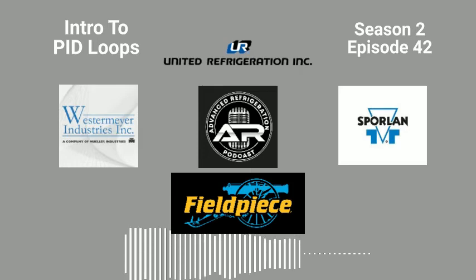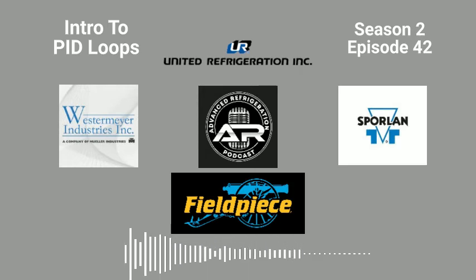With CPC stuff, you're going to control a valve actuator and you're using an EPR board. That EPR board update rate is 15 seconds from the factory, so you need to change it to 2 seconds. So even on CPC, you have a 2-second update rate on the input, a 2-second update rate on the EPR board, and now you have the loop sequence control, which is going to be your main driver of the main PID loop, and it's 15 seconds. So you need to change that to 2 seconds.